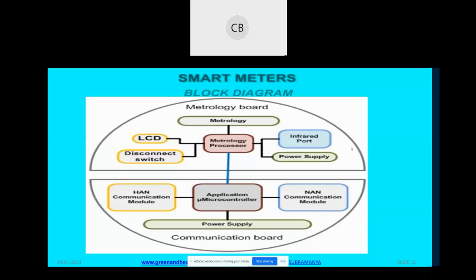The smart meter comprises two main parts: the metrology part and the communication part, also called the metrology board and communication board, which are integrated together. The metrology board consists of a microprocessor, an LCD display, and a connection/disconnection switch built into the meter. This switch has a 100 amp capacity, which will throw open or disconnect the circuit when load management is not happening properly.